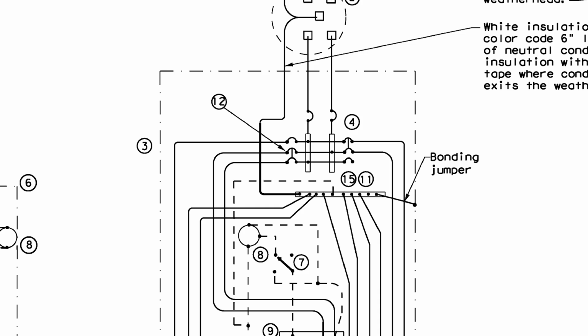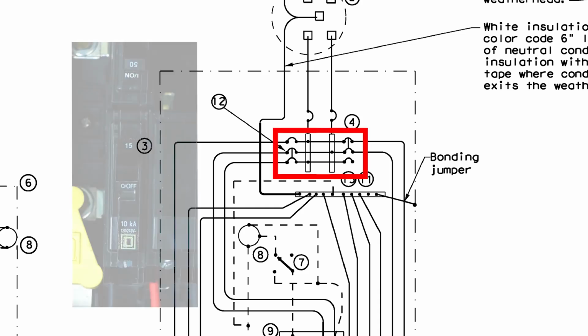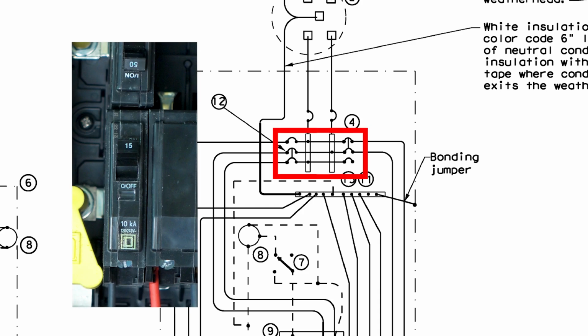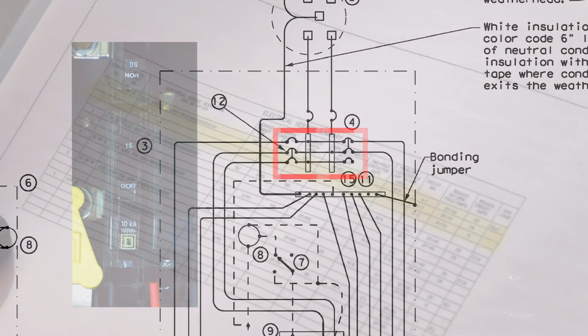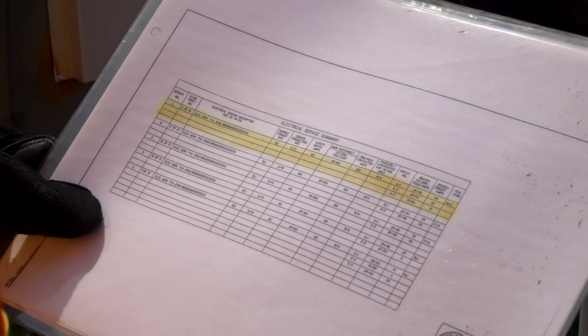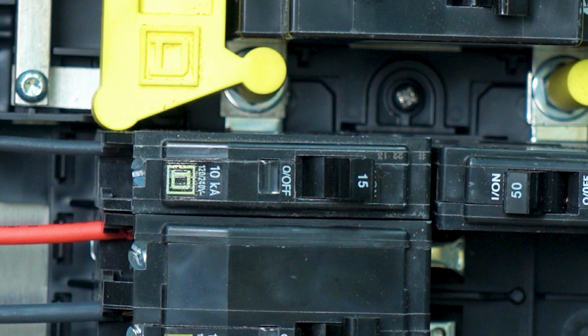Next, the inspector should inspect the branch circuit breakers. The ampere rating of each branch circuit breaker and the specific load served should be confirmed by a review of the panel's schematic diagram. The ampere rating for each circuit breaker is printed on the end of the breaker's operating handle. The Type D service with a load center will have plug-in type breakers, commonly called stab lock.